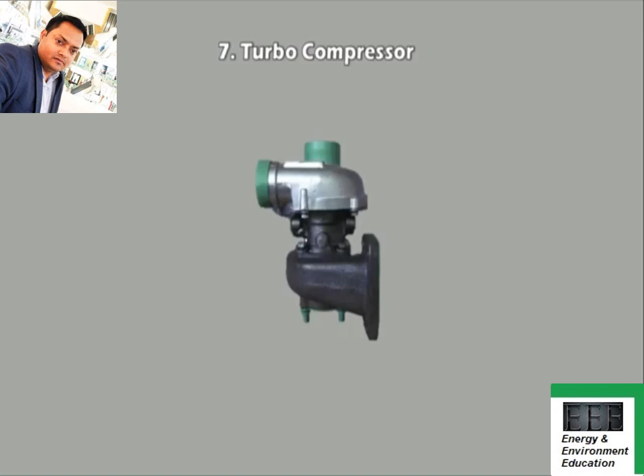The remaining kinetic flow energy is afterwards mostly converted into pressure in the diffuser. The compressed gas is then either collected in a volute or transferred to a second compressor stage with the help of a return channel. In figures, the components of a one-stage, centrifugal turbo compressor and the close-up of an impeller including blades are shown.